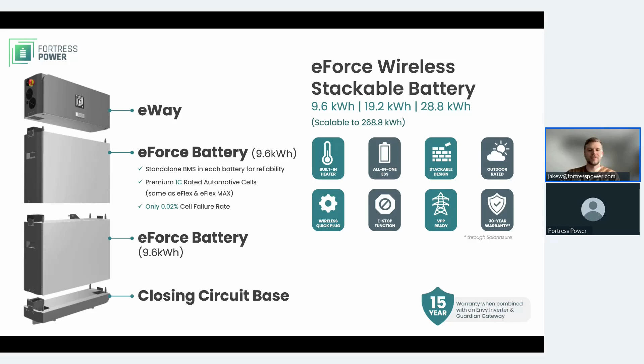Inside the E-Way, we created another feature where it acts like a wire gutter or trench, where you can put the conduit inside of it. So you have the punch-outs on the left and the right side and on top. This comes with built-in 750 amp bus bars, so you can parallel multiple units.